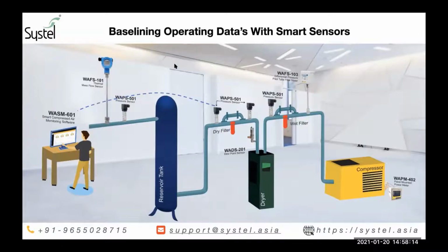And the other sensors, like the digital pressure sensors, understand the pressure drop happening across your dryers, and the dew point sensors understand the actual pressure dew point that you're producing from your refrigerant or desiccant dryers. Here, another fact is that usually the end user assumes that whatever is displayed on the dryer is actually the dew point. There is quite a difference between the two.